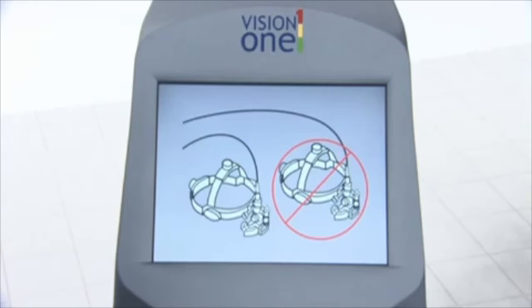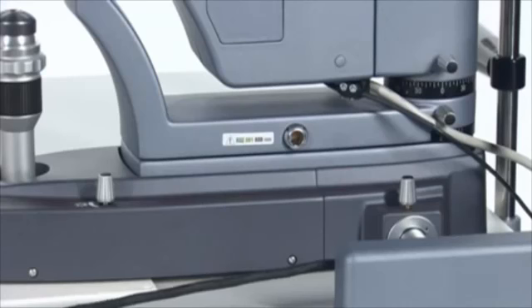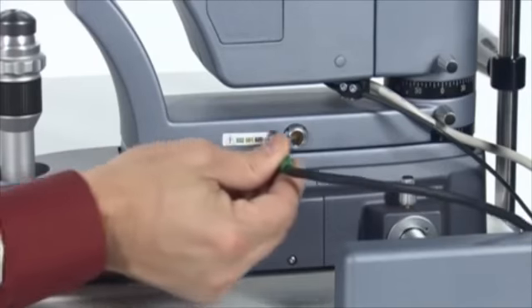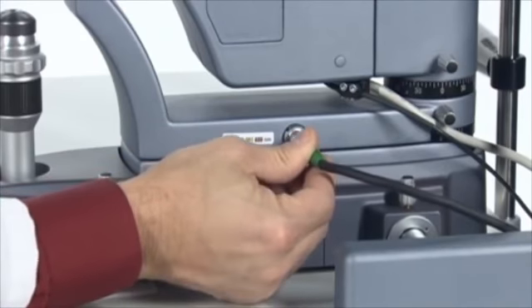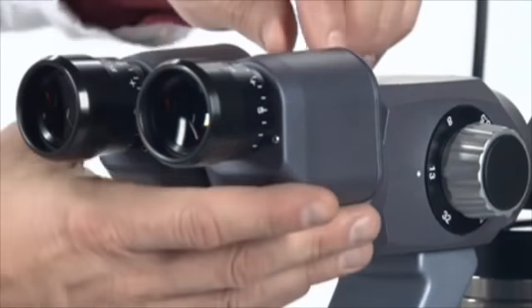If two of the same type of delivery devices are connected to the laser console, this symbol displays on the control screen until one of the devices is disconnected. If no delivery device is properly connected, the following illustration displays on the control screen until a delivery device is properly connected.